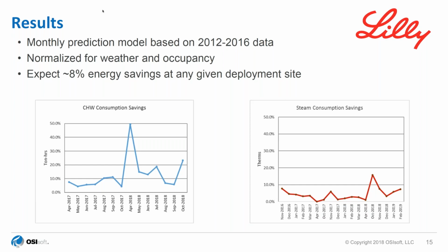The other thing this built for them was, when you think about all those facilities, the energy managers are not the facility managers. So they didn't want to be a burden. So the energy managers developed this themselves. They created what we'll call templates and math, the fault rules and the analytics. And when they went to the facility manager, they said, look, we just need to install this small piece of software to get these 10 values out of your system. It'll have no interface. In this case, I think they used the BACnet interface.